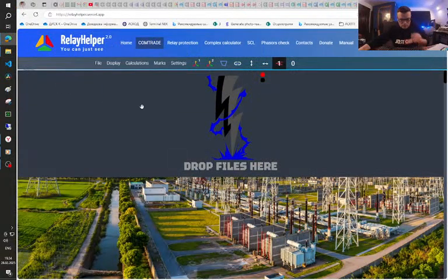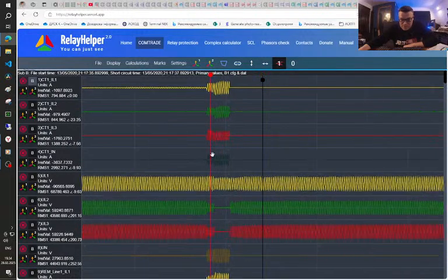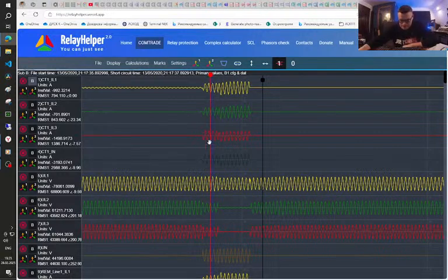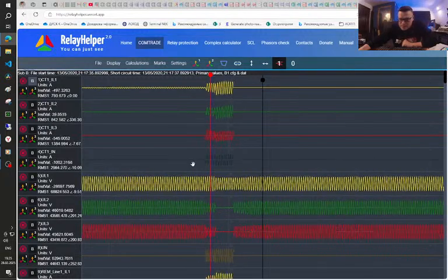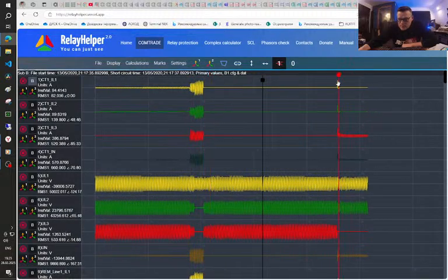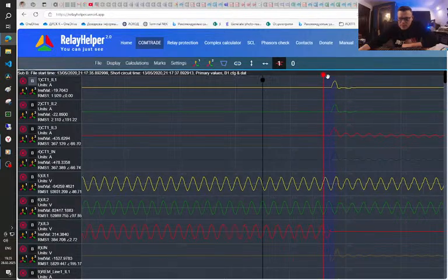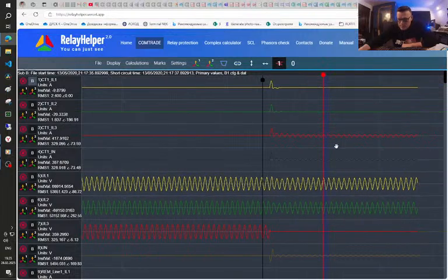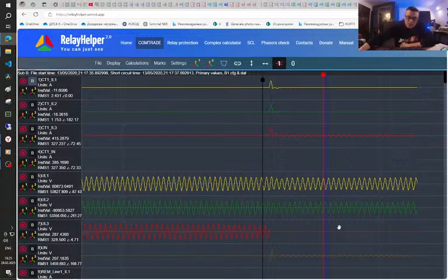substation B. So here you can see a little bit different picture, because in the beginning we see that there is a two-phase short circuit, and also big enough current on phase A. On phase C it is 1386, and on phase A around 700, on phase B around 800, and we can see a pause and some strange spike after that, and then very little current and almost zero voltage.